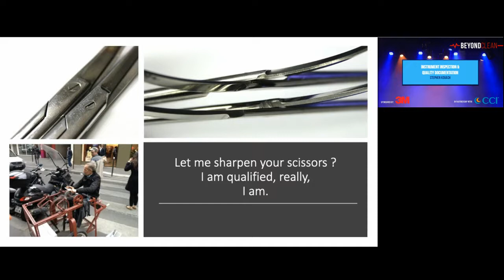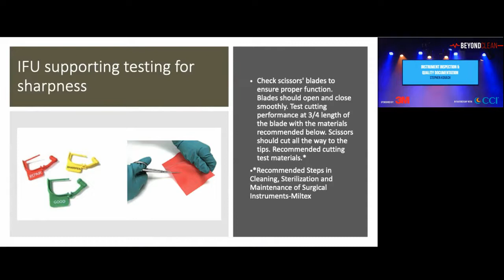Check scissors blades to ensure proper functioning. Blade should open and close smoothly. Test cutting performance at 3/4 lengths of the blade with the material recommended below. Scissors should cut all the way to the tips. And this is from another manufacturer, and they actually tell you what you can use. So again, you're supposed to be testing it. You should have this available for your staff.